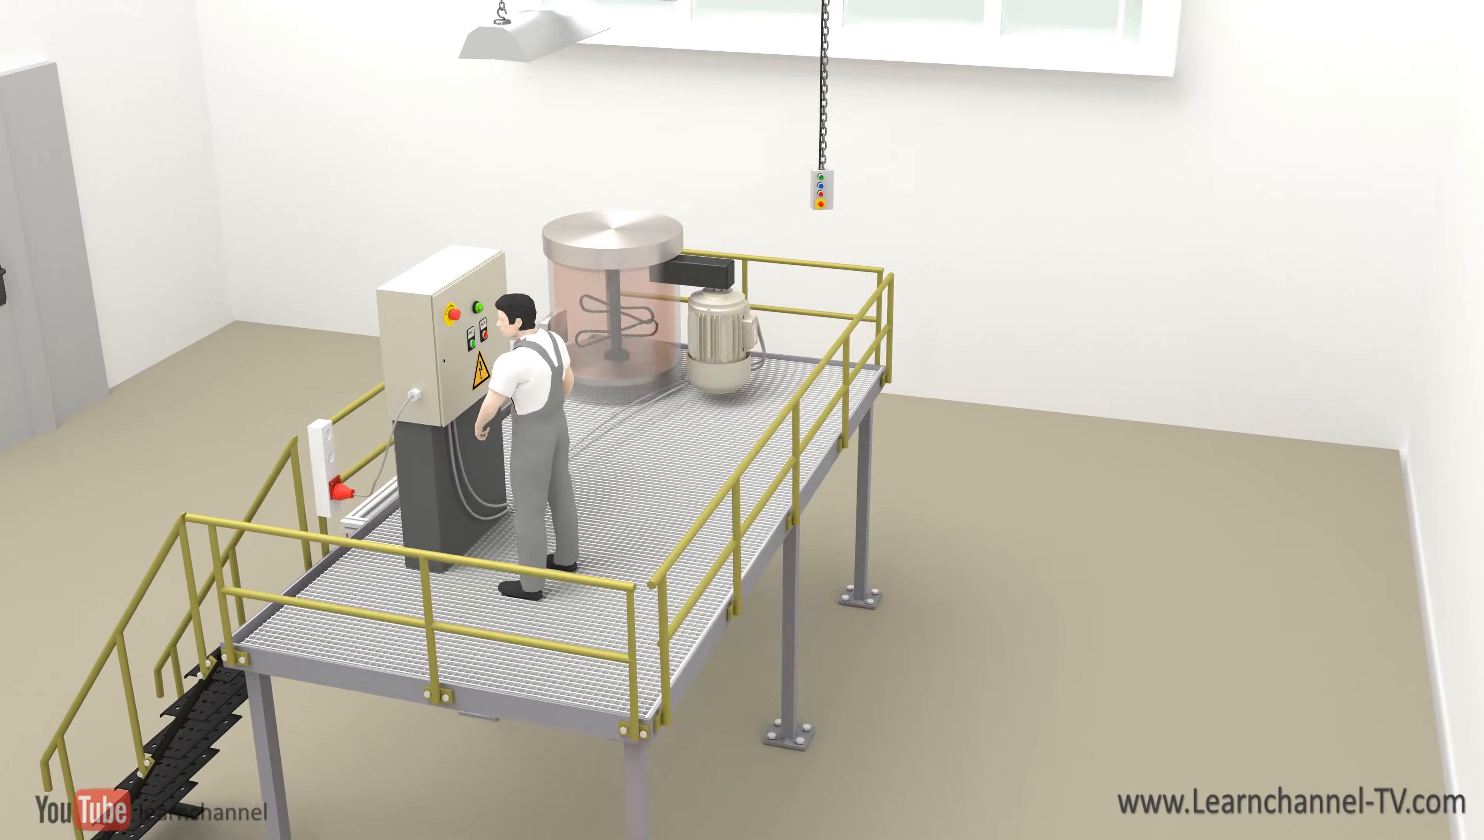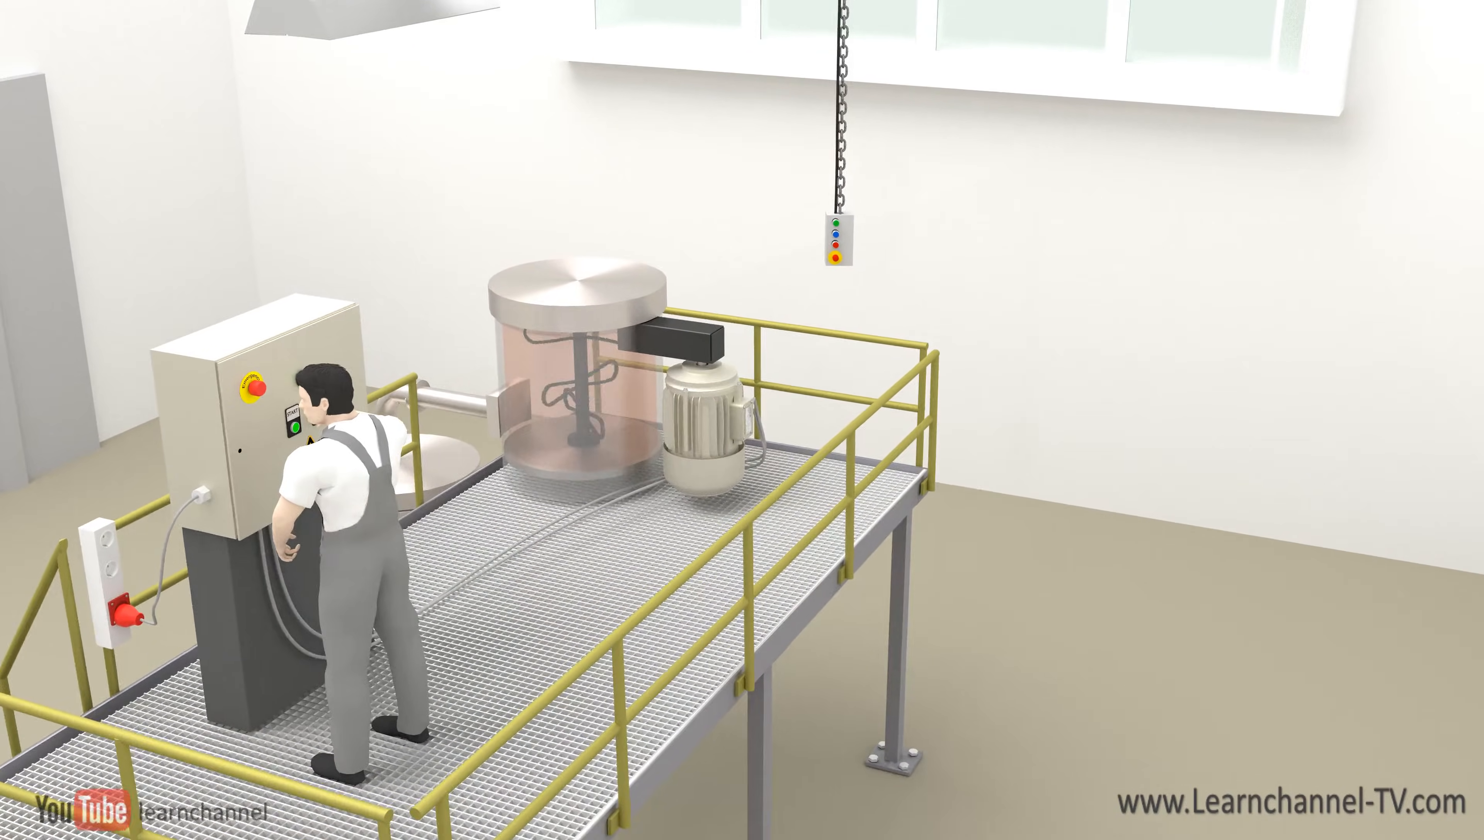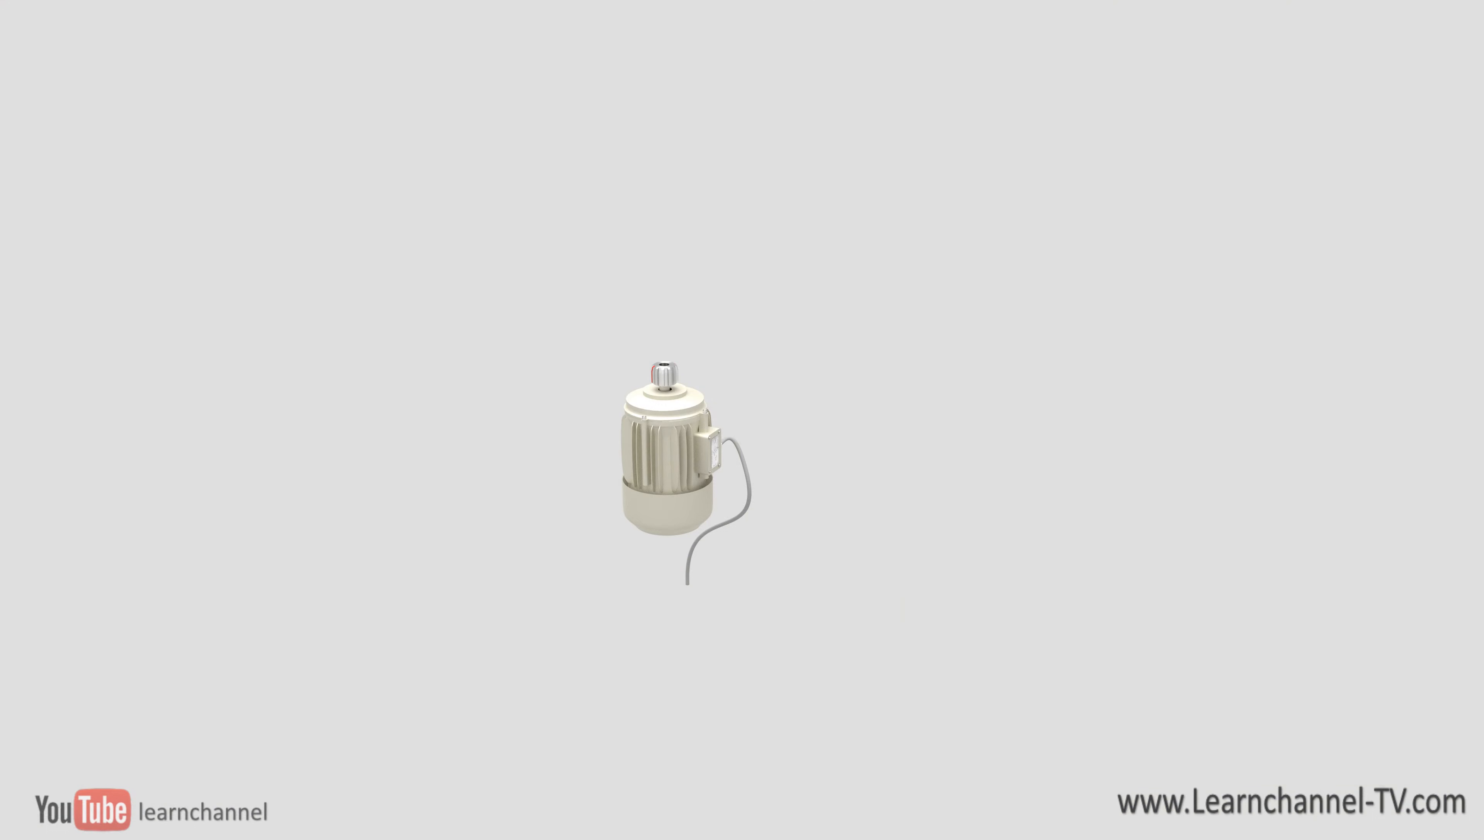The three-phase induction motor is probably the most commonly used electric motor in the industry. The problem with this motor is the high starting current, which is seven to ten times the rated current.